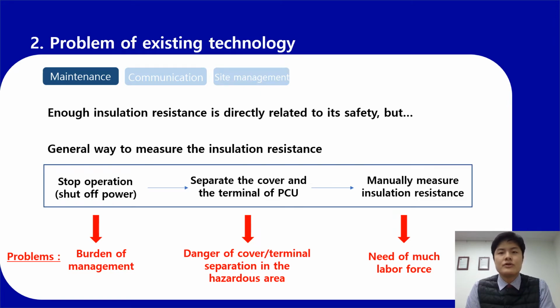I'll explain the general way to measure insulation resistance. Existing technology cannot measure the insulation resistance while the electric current is applied. So the power should be shut off first. After that, a person should open the power control unit cover and separate the terminal, and then manually measure the insulation resistance by using the measuring device.